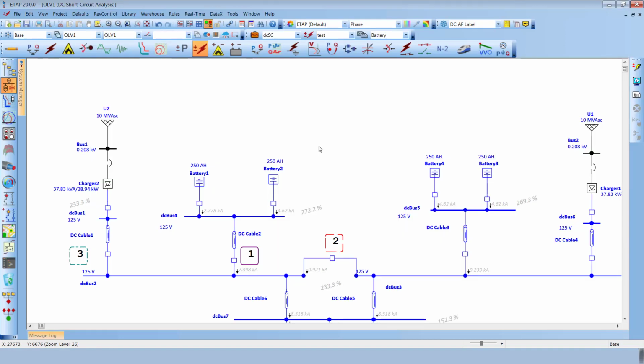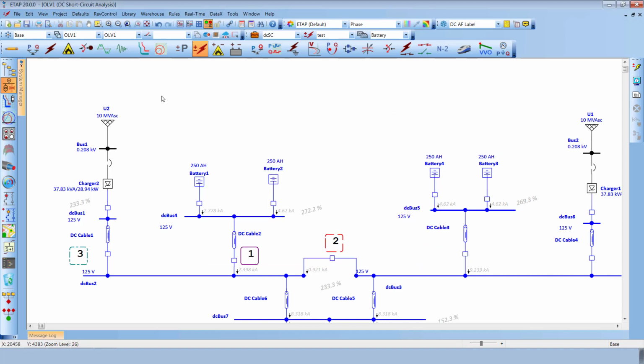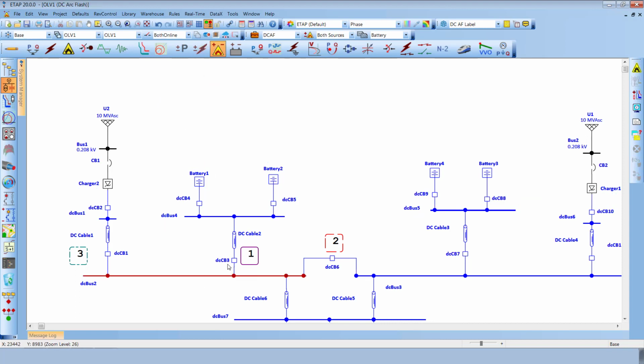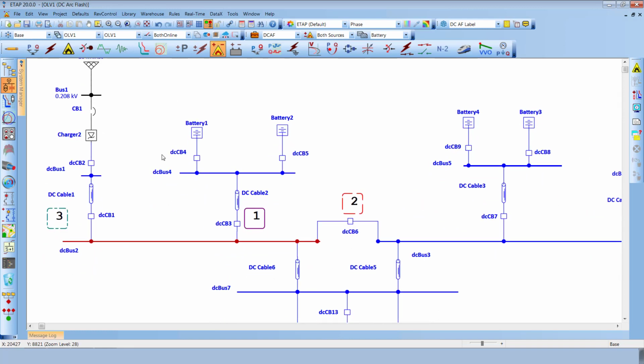For the battery sources and the charger sources, the modeling option could either be used based on an individual charger contribution from the editor settings, or a global setting that is used for batteries or chargers correspondingly and configured in the short circuit study case. With that, let us move on to our original scope on evaluating the arc flash incident energy at bus 2 depending upon several configurations and the source's contribution to the faulted location.